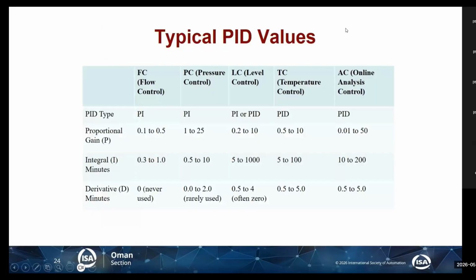So here are some typical PID values. Again, this is theory. It's good to have a reference, but don't just take it and implement it in the plant blindly. It can vary. But this is something to help you have a reference. So for flow controllers, typically proportional gain is from 0.1 to 0.5. Again, this is proportional gain, not proportional band. We can see pressure controllers 1 to 25, level 0.2 to 10, temperature 0.5 to 10, and analyzer 0.01 to 50. Integral: flow controller 0.3 to 1, pressure 0.5 to 10.